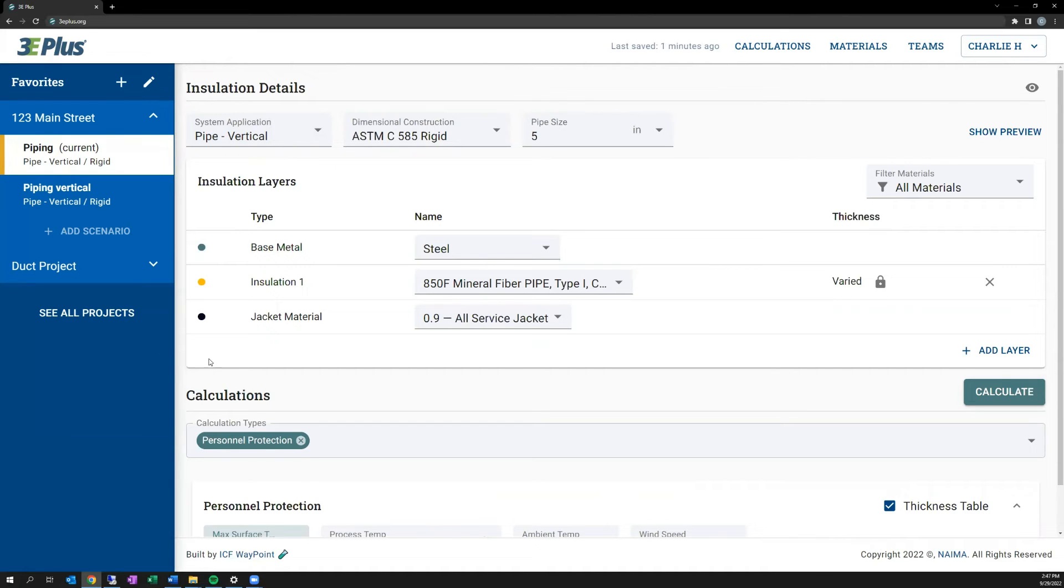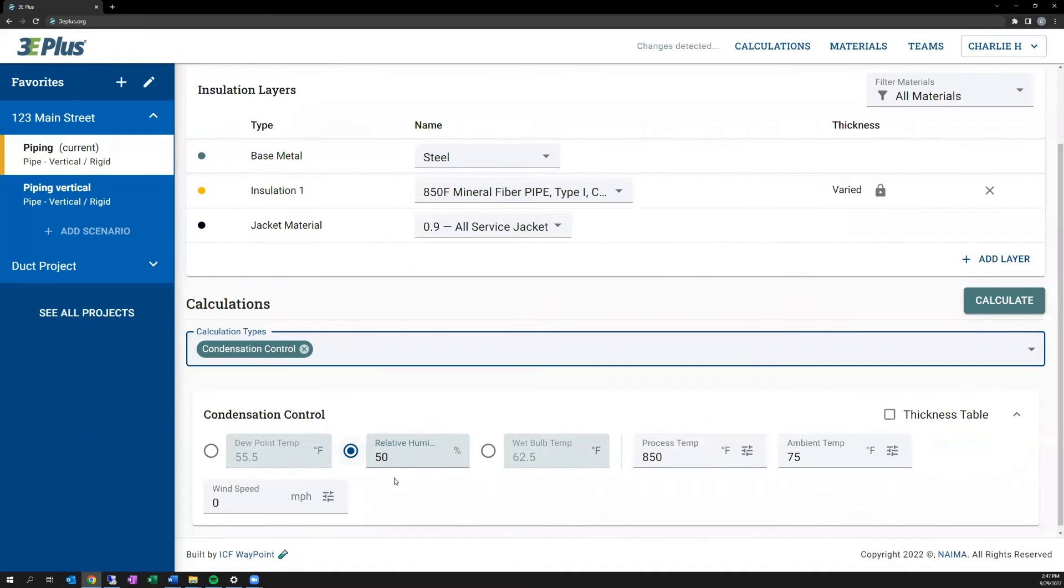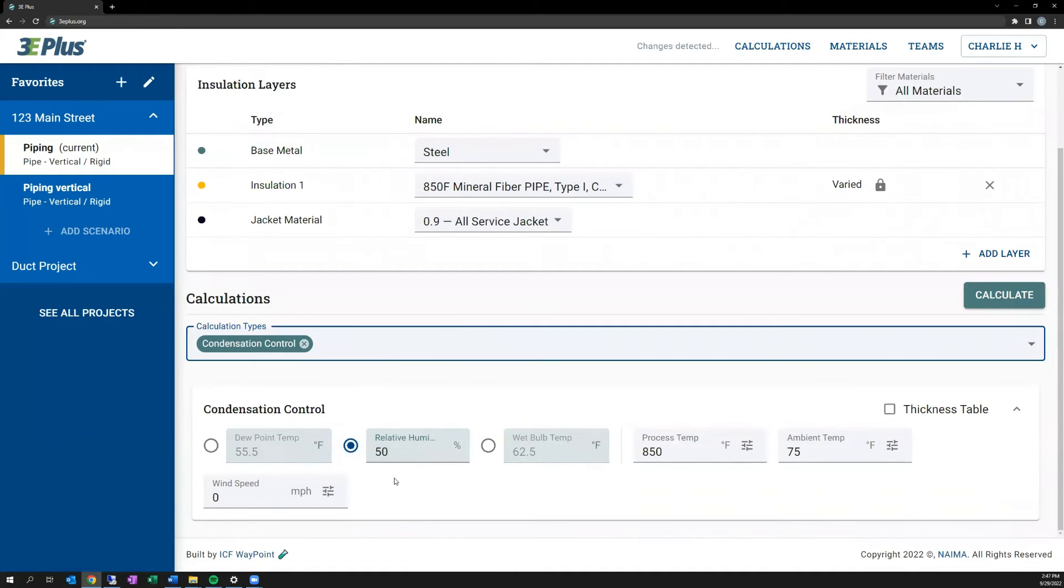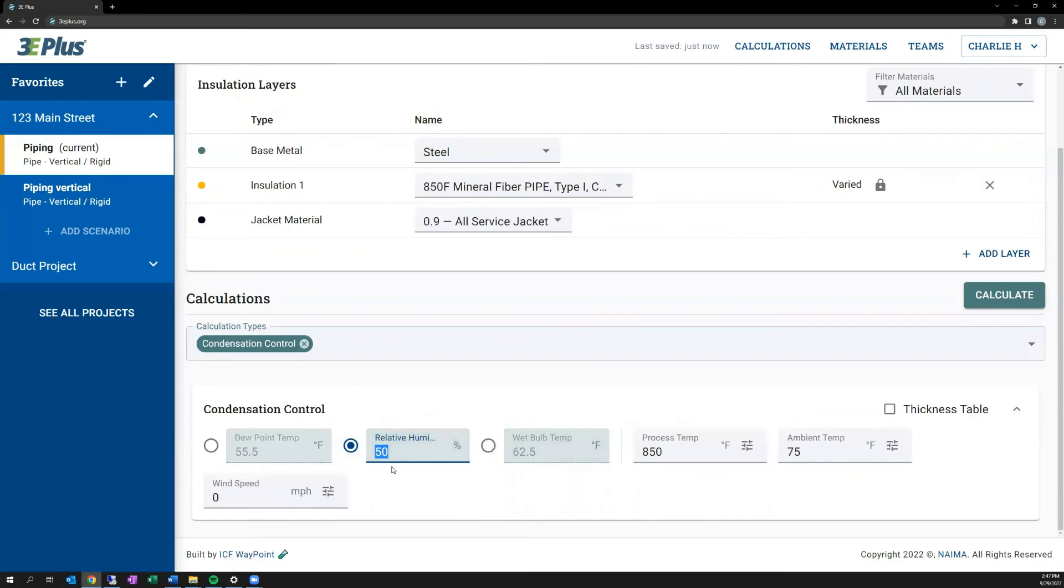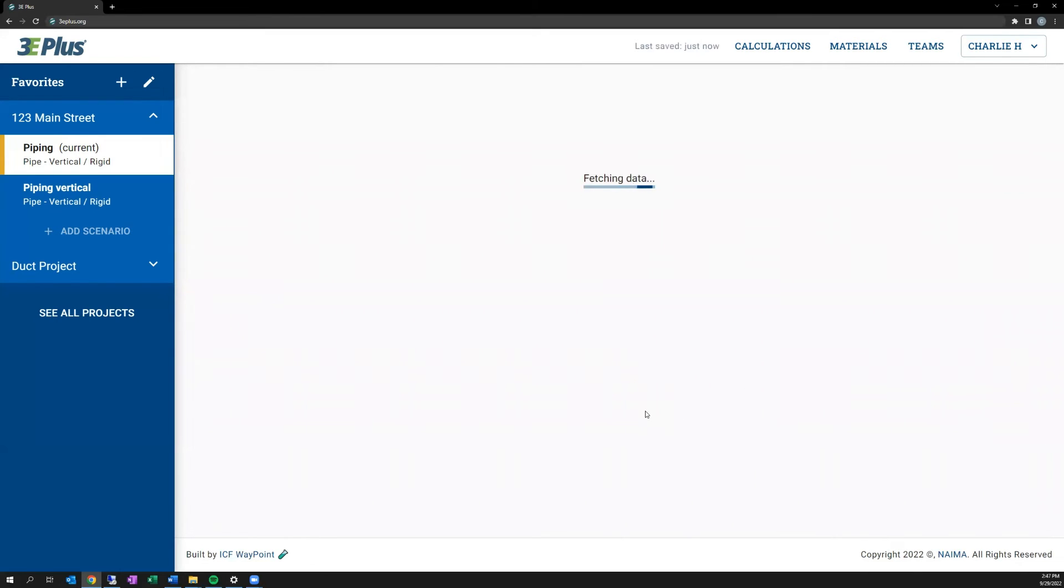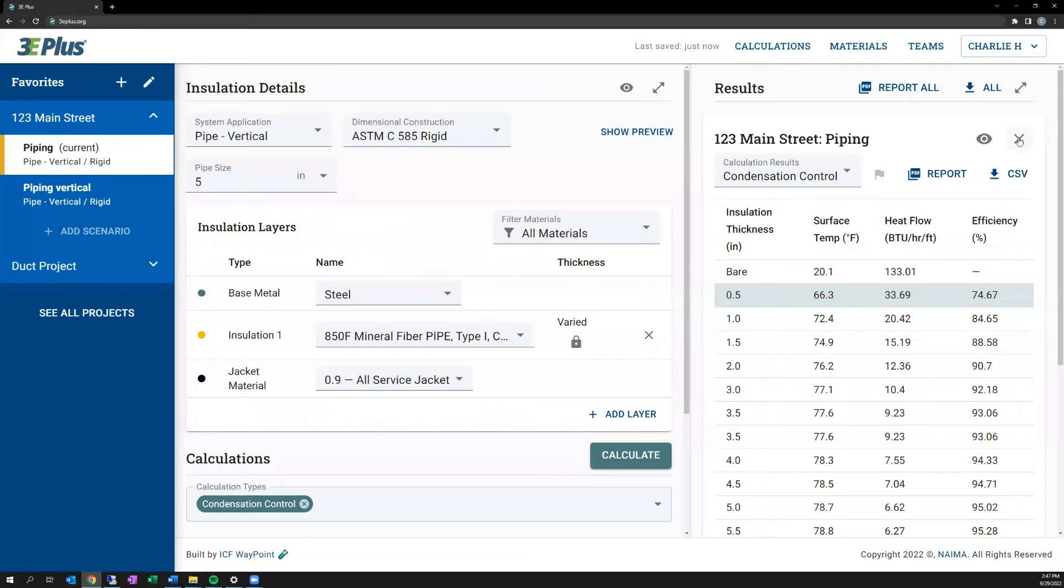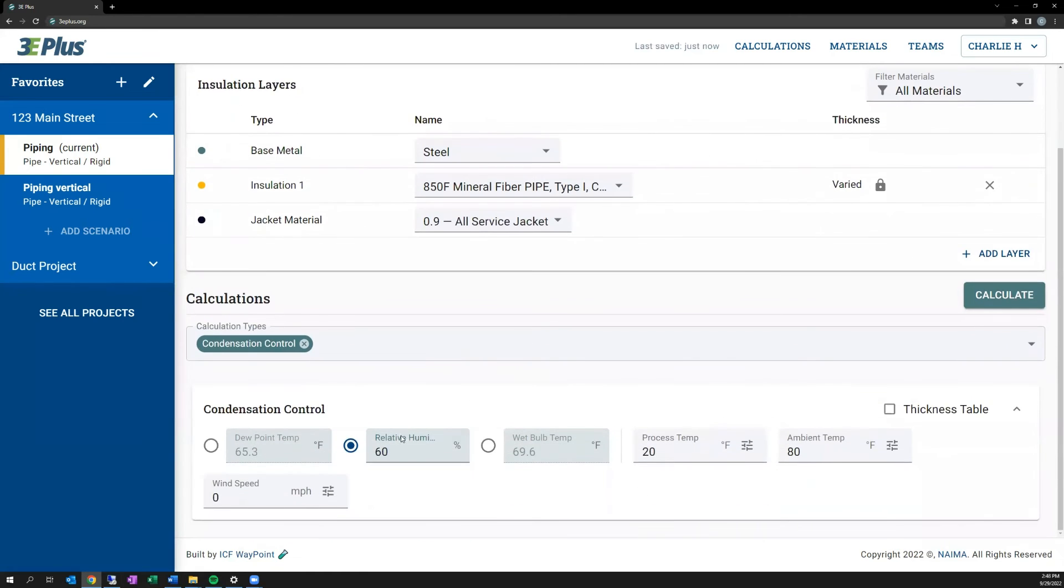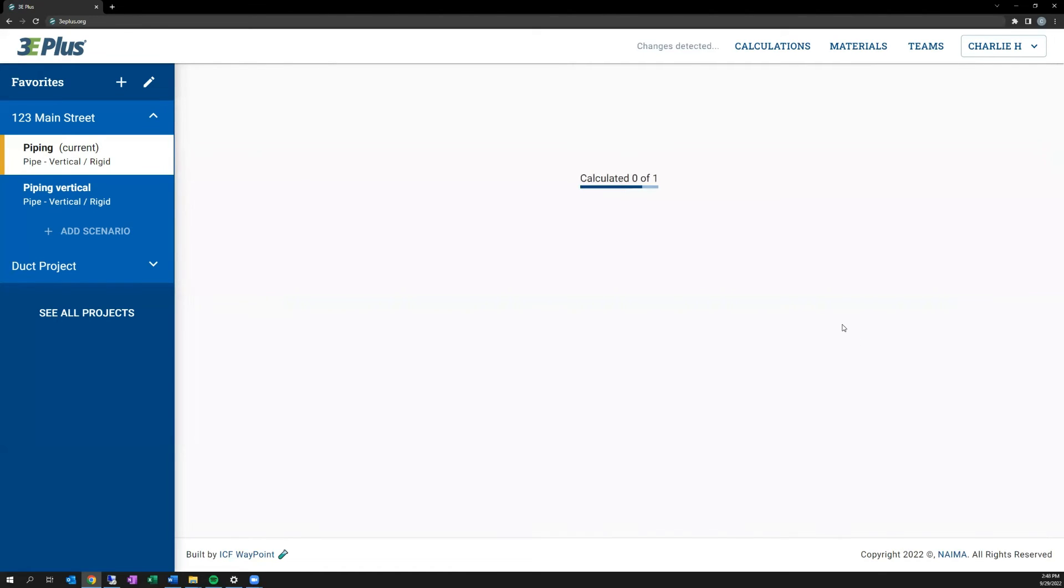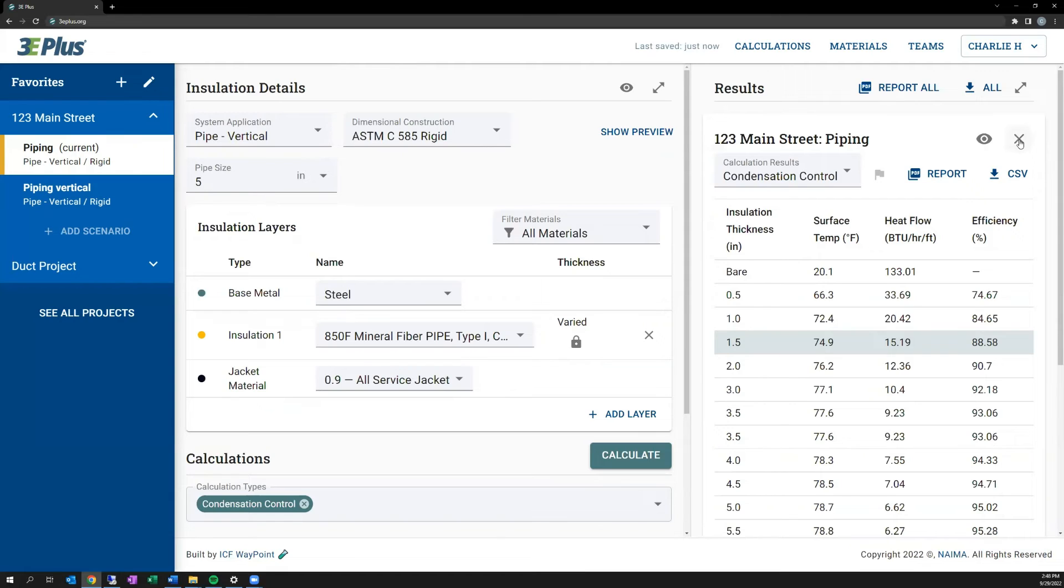Additionally, moving on to condensation control, another target calculation. You can see here that there are different target inputs, with options for dew point, relative humidity, and wet bulb temperature. In this case, I'm going to say the relative humidity is 60%. Typically, condensation is done on colder process temperatures. So I'm going to say a process temperature of 20 degrees, an ambient temperature of 80 degrees, and zero for wind speed. I hit calculate here. It shows you how much insulation is needed to ensure that condensation does not occur in that pipe. Now, if I raise the relative humidity, you can see that the results will require more insulation to ensure that the outer surface of that insulation is above the dew point temperature.